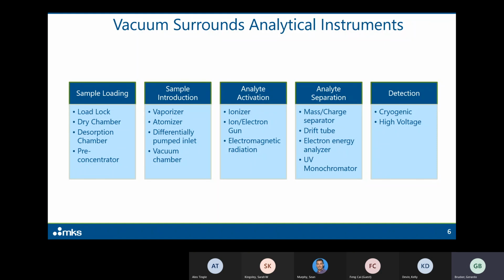So basically, the sample loading section requires vacuum. It could be a load lock, it could also be a drying chamber where I dry the sample before I bring it into the rest of the vacuum system. It could be a desorption chamber. It might be a DESI experiment or a DART experiment where I'm just desorbing ions by bombarding them with metastables. It could also be the pre-concentrator in a gas chromatography system.